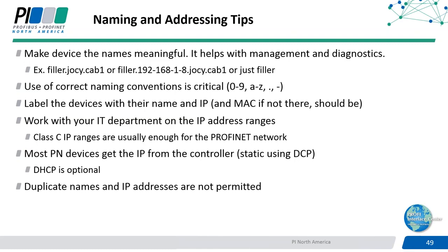Of course, label your devices out in the field with their name and IP address, and put the labels on your network topology diagram too. If you don't have the MAC address on the device—though most of the time on PROFINET devices it will be stamped on the device—if it's not there, you probably want to put that out there too.